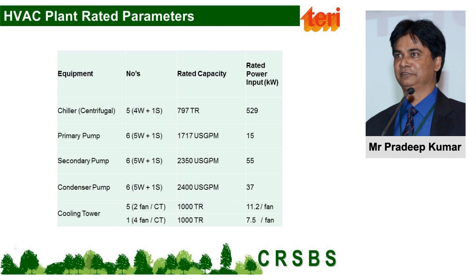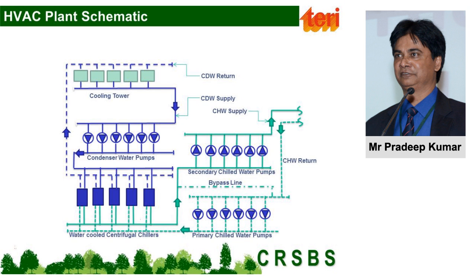In this, you can say there are 5 centrifugal chillers of 800 TR being used with a 2 loop system, primary and secondary. Each loop has 6 pumps, primary on constant speed, secondary on variable speed. The condenser pumps are of course on constant flow, but for the cooling tower, VFDs were installed. And if you look at the schematic, it looks like this.